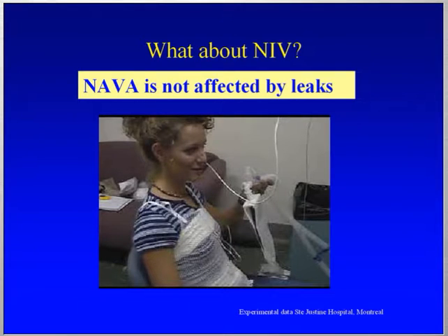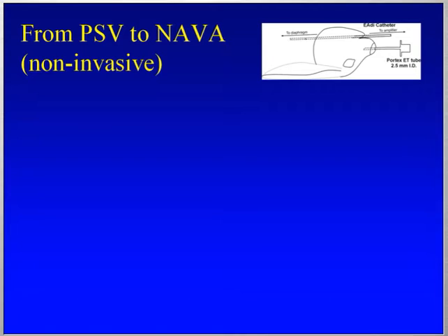And the point I wanted to make with this short video clip is that NAVA is a pneumatically independent mode. It is neurally controlled, and therefore it is not affected by leaks. And this opens up a whole new field and possibilities for non-invasive ventilation. And this is the work we're doing right now.